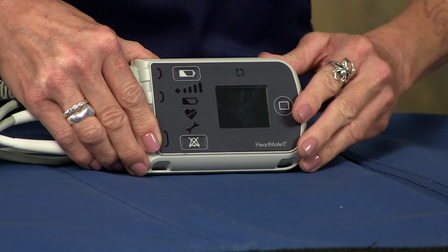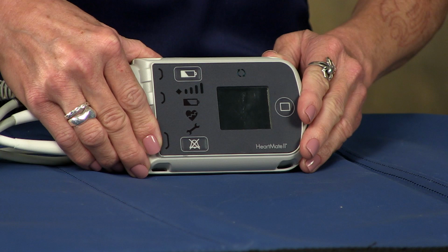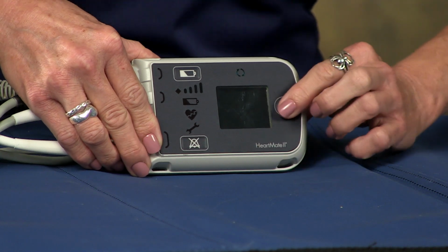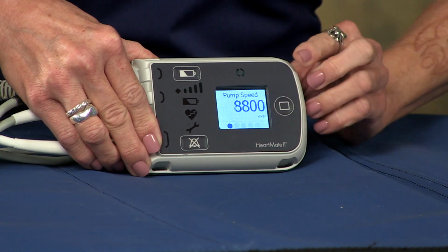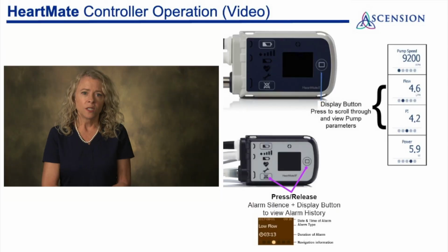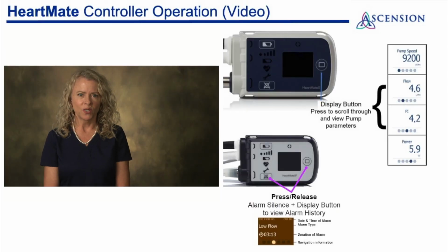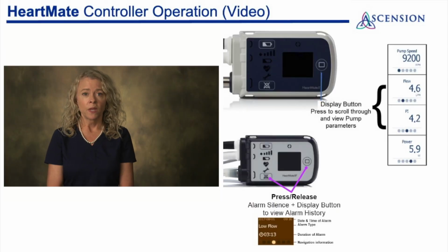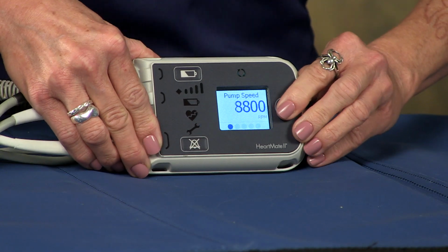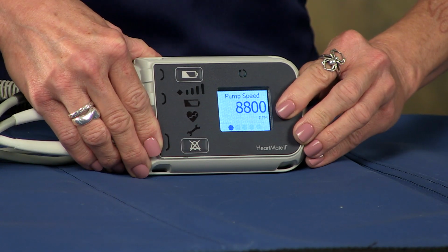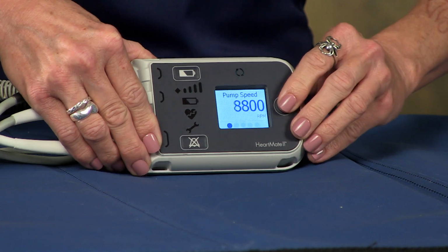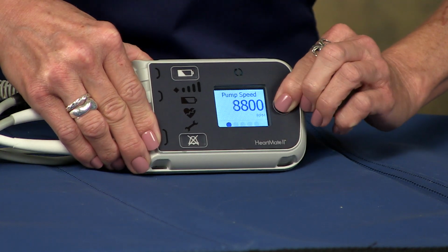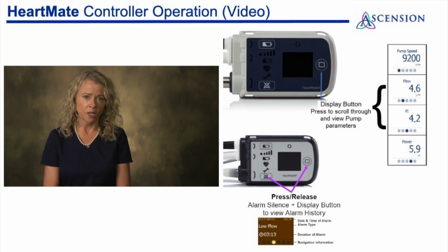Now I want to show you how to check the VAD numbers. This square button is called a display button. When pressed, it will scroll through screens to display information about the VAD. It's important to note that you cannot make changes to these numbers. You can only view them. The first number is the speed the VAD motor is spinning. It's measured in RPMs like your car. The speed sometimes fluctuates anywhere between 50 and 150 RPMs.